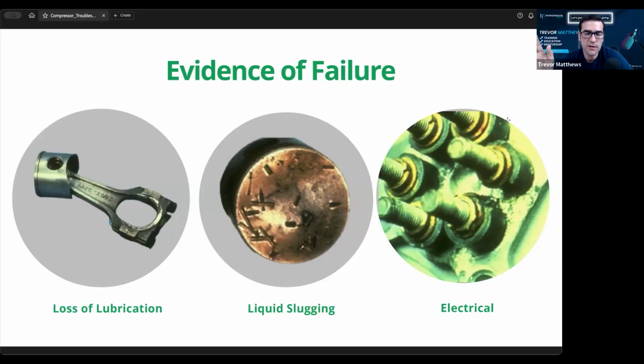Well, there's lots out there. So I work with a lot of people on the large commercial stuff, industrial stuff, and you've got to send this out to the lab. Like, you can go to Sporlan and other manufacturers, you go to United, Johnstone, RSL, Master, whoever, and you can buy a little acid test kit for the oil. You won't do this on little tiny 1 horsepower units or 5 ton, but on a rack system where you've got dozens of liters or gallons of oil, you're going to want to check that.